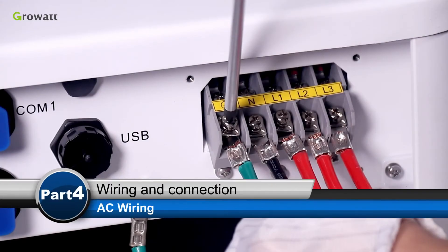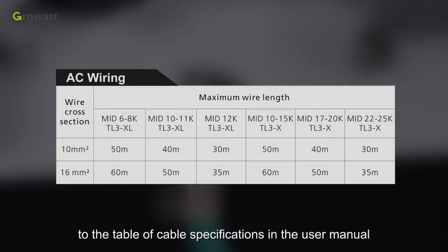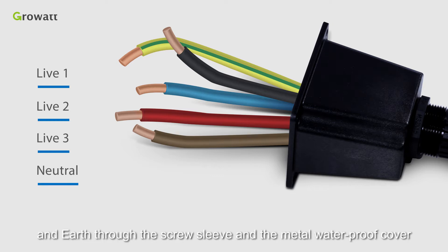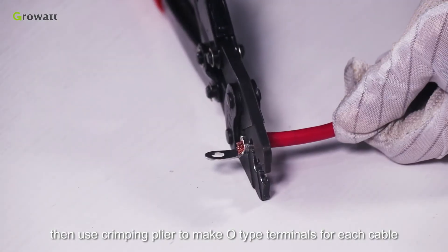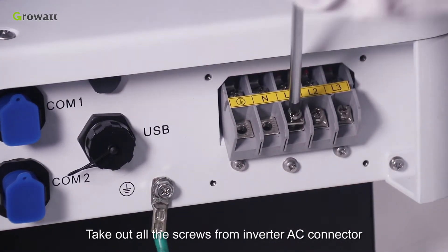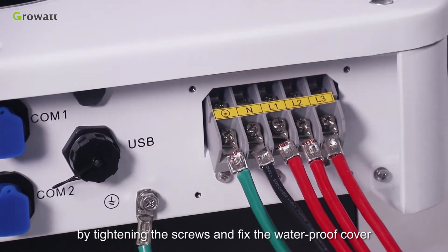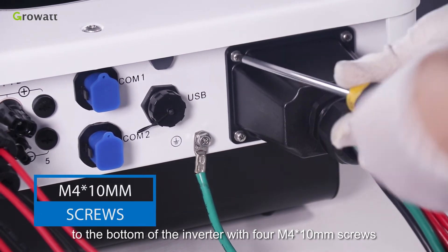AC wiring. Please choose eligible cables for AC wiring referring to the table of cable specifications in the User Manual. Thread the five cables — Line 1, Line 2, Line 3, Neutral, and Earth — through the screw sleeve and the metal waterproof cover. Then use gripping pliers to make O-type terminals for each cable. Take out all the screws from the inverter AC connector. Lock the cables onto the inverter AC connector by tightening the screws, and fix the waterproof cover to the bottom of the inverter with four M4 by 10 mm screws.